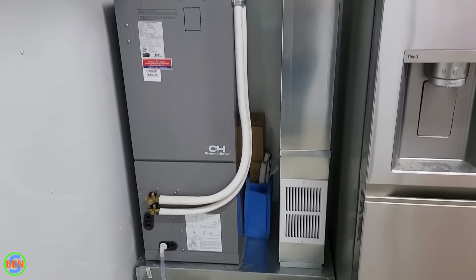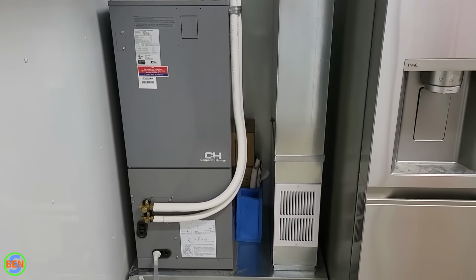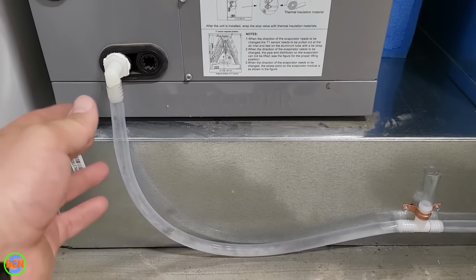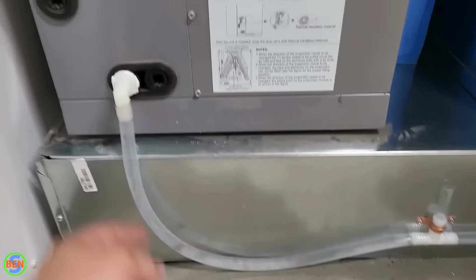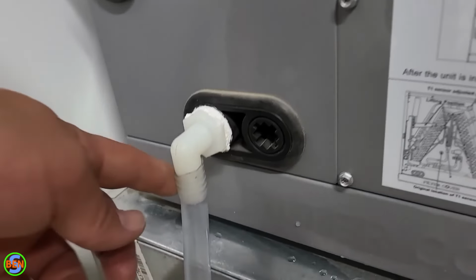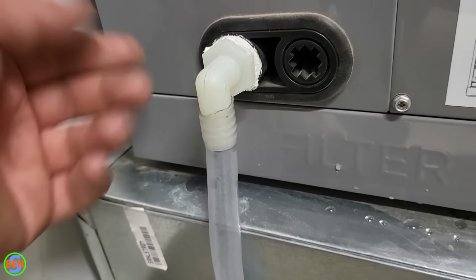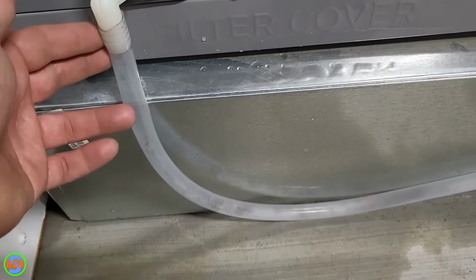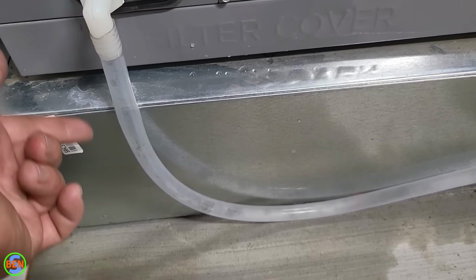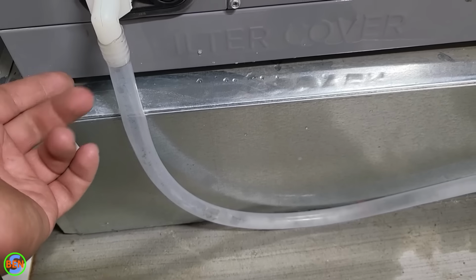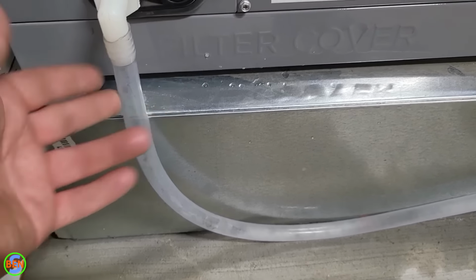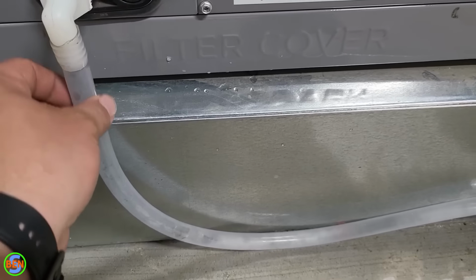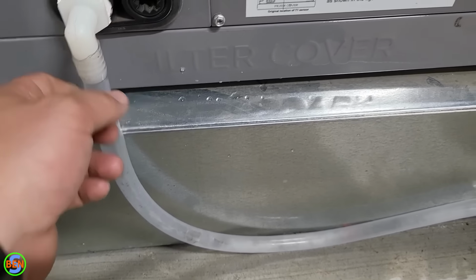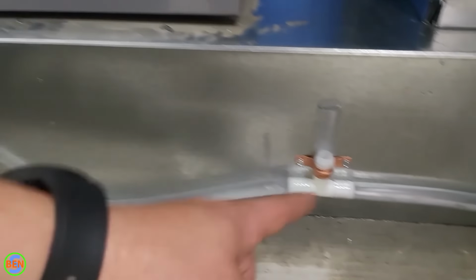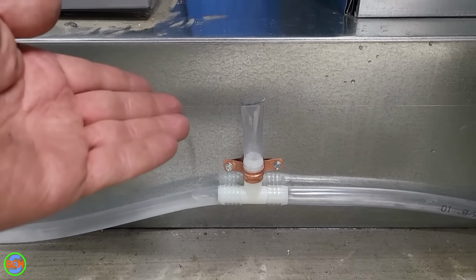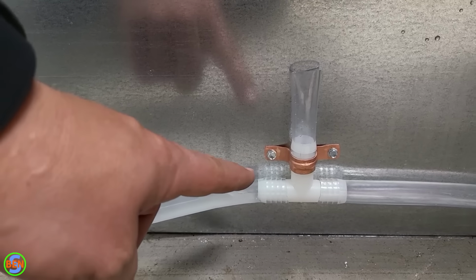For the air handler unit, the condensate drain situation is a little bit different. In our case, we are using 5/8 vinyl tubing, so this is a 3/4 by 5/8 barb fitting that we adapt to, and we like to use this type of material just because you can easily inspect it and disassemble it in order to service the line. So if you need to clean this line out, you can just pull this off of here and blow air through it or whatever. And then you'll see right over here, we have this T, which is acting as a vent, and we've got this held up off of the floor a little bit.